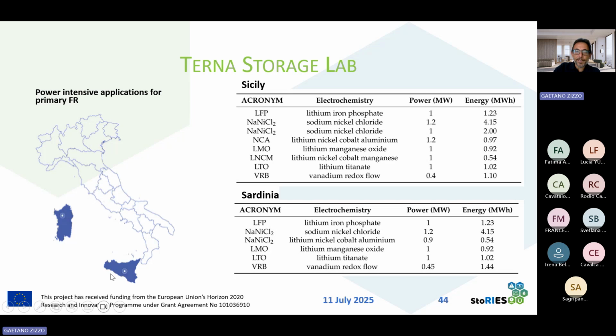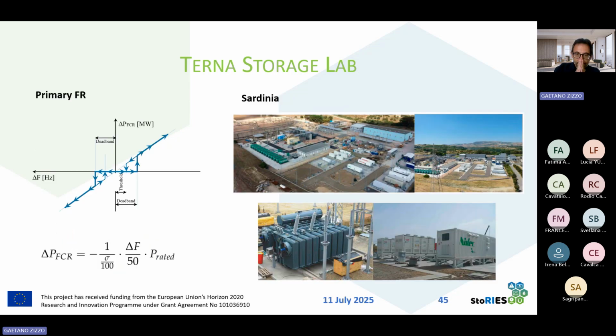These are power-intensive services provided by these technologies in Sicily and by these technologies in Sardinia. You can see that the installations comprise power that for each technology is around 1 megawatt, with different charging and discharging times. The interesting results have been obtained testing each technology for primary frequency regulation. So this is the activation curve of the voltage source converter connected to the storage systems, and this was the function that represents this graph.